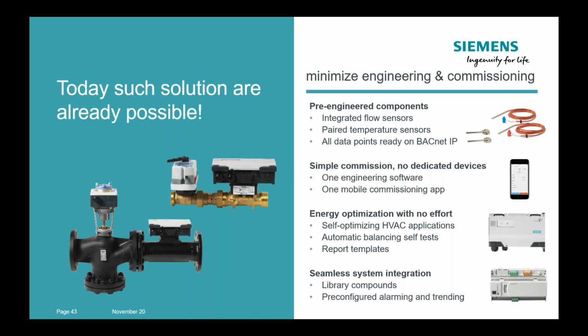And we are still working on energy optimization topics. We have the DeltaT control, but we are looking for automated functionalities to limit the flow control, to preset the flow. And also here we have the capability for automated balancing tests, and you can even do reports locally, so that you are assured that the presetting is done well and that the flow is available there. So overall, intelligent valve solutions are really a well-shaped package, and not only DeltaT control.